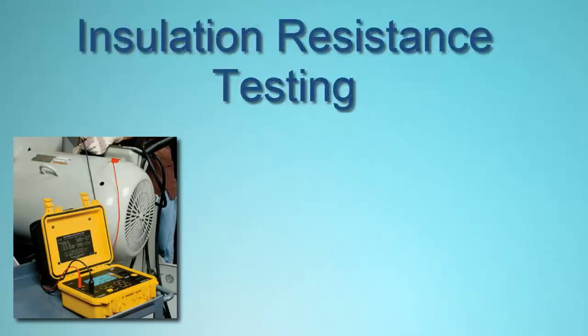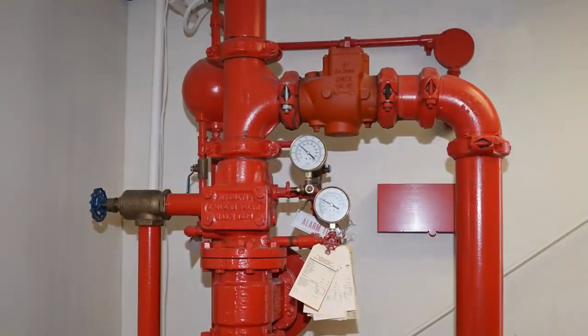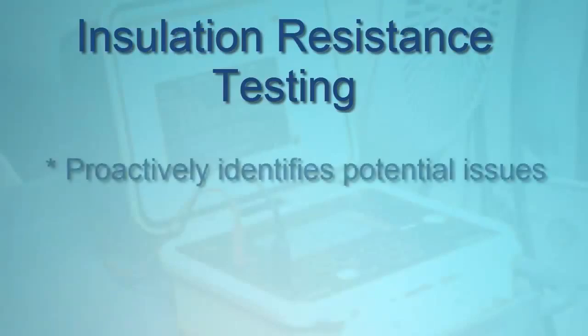To assess and monitor insulation integrity, several tests have been developed. These typically involve injecting a test voltage and then measuring resistance. This stress tests the insulation, similar to applying high water pressure to plumbing to test for leaks. A regular program of resistance testing can detect insulation deterioration, so it can be identified and addressed before it becomes a major problem.